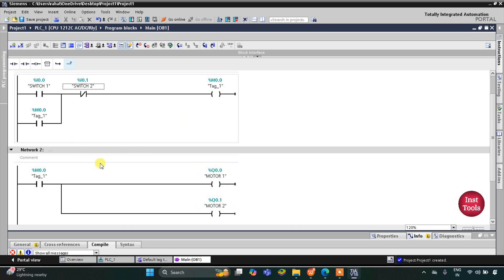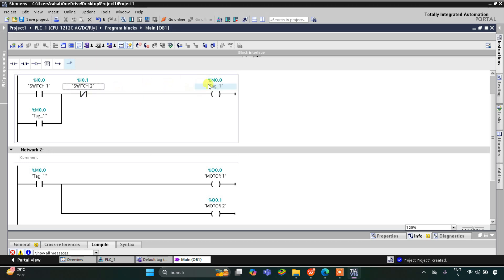When motor 1 and motor 2 are on because of M0.0, and when switch 2 is pressed or turned on — as it is a normally closed contact, in its true state it will not allow current to flow through it. As a result, M0.0 turns off, which in turn turns off motor 1 and motor 2. When switch 1 is pressed, current flows through it. Switch 2 is in false state, and as a normally closed contact in false state it allows current to flow, so M0.0 gets true, turning on motor 1 and motor 2. When switch 1 is turned off, M0.0 is still true due to latching, so current still flows. M0.0 remains on after turning off switch 1.